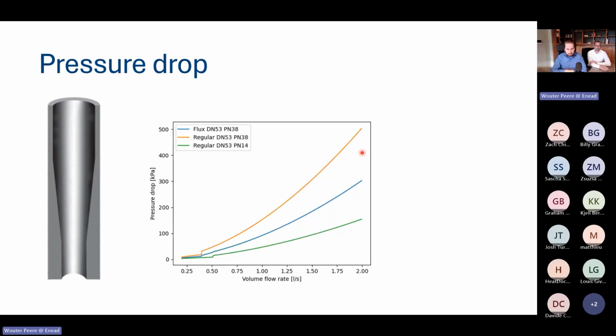Now this is for a constant flow rate. If we say, okay, let's take a pipe of 500 meter and let's vary the flow rates. And here you can see clearly that our flux pipe is in the middle of both our two edge cases, where we see that our regular PN38 would transition to turbulence sooner. That's this sudden jump. And that's, of course, because the wall thickness is thicker, the inner diameter is a little bit smaller, the flow velocity is a little bit higher, so it gets to turbulence sooner.